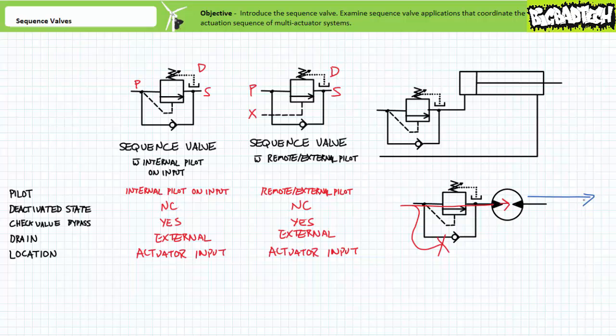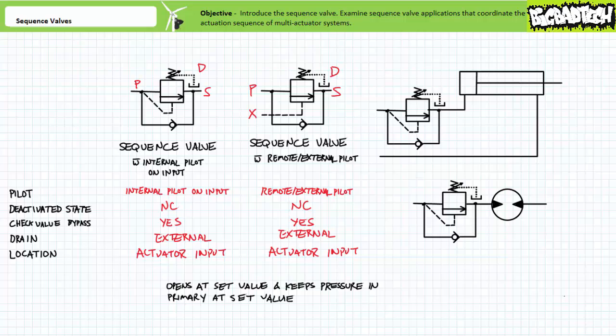Similarly, this sequence valve is on the input of this bi-directional hydraulic motor when flow travels left to right. Only when pressure on the input port exceeds the set value does the sequence valve open and spin the hydraulic motor in one direction. When flow switches direction, the sequence valve is bypassed through the check valve bypass, and the hydraulic motor spins in the opposite direction with no pressure precondition. Note that normally closed sequence valves open when pressure on their pilot port rises above the set value. Most sequence valves typically keep inlet pressure in the primary circuit at the set value and stay open as long as there's a differential between input and output. Once pressure equalizes at the input and output, the sequence valve is considered fully open and pressure can then rise to the setting of the main pressure relief valve.